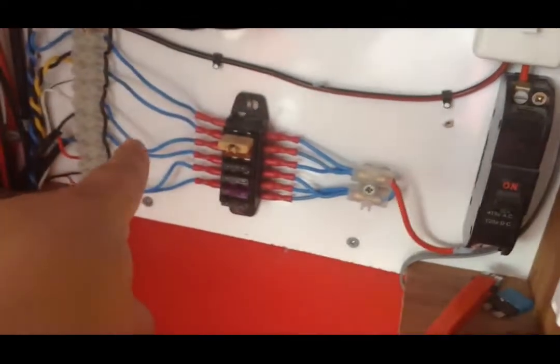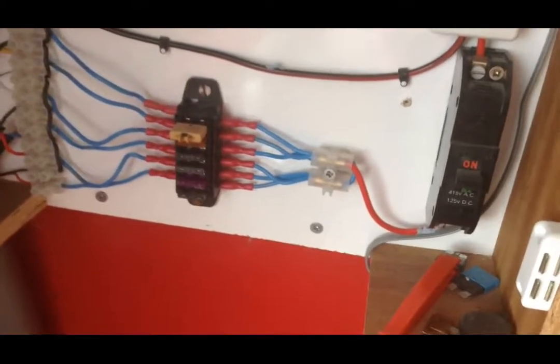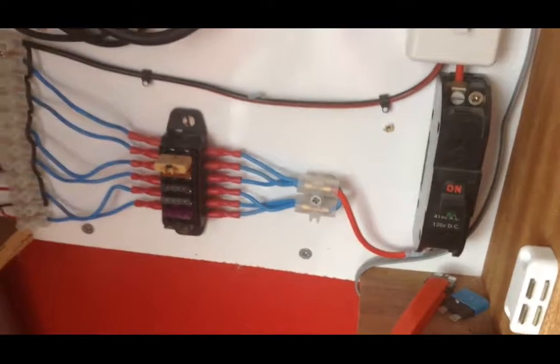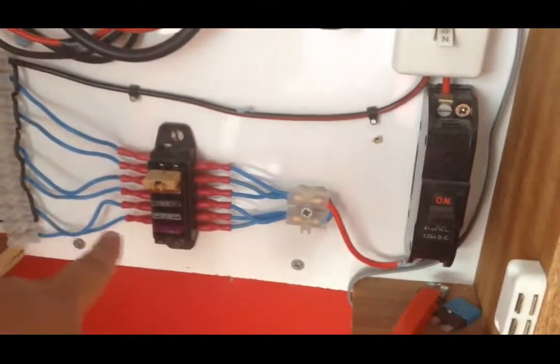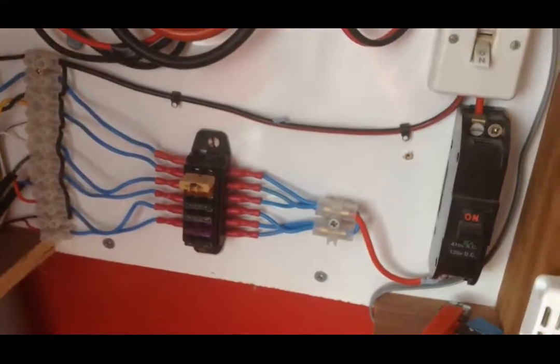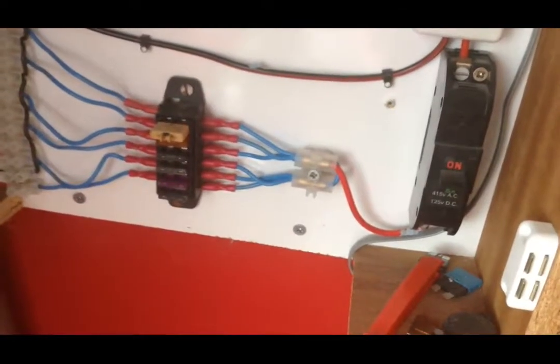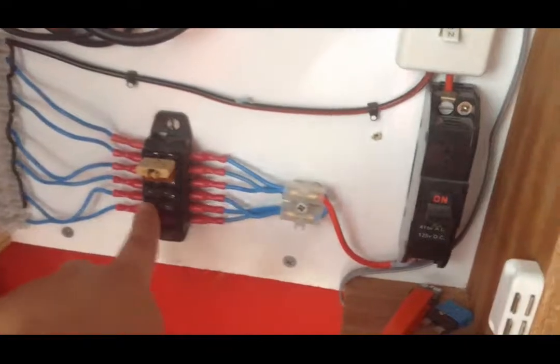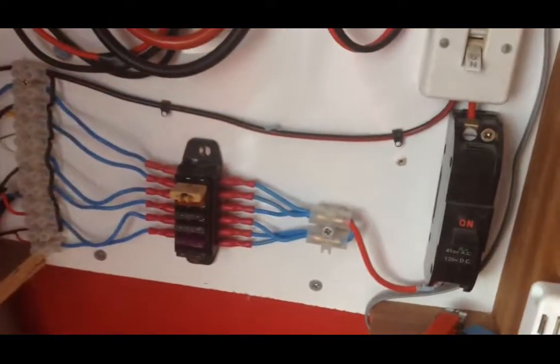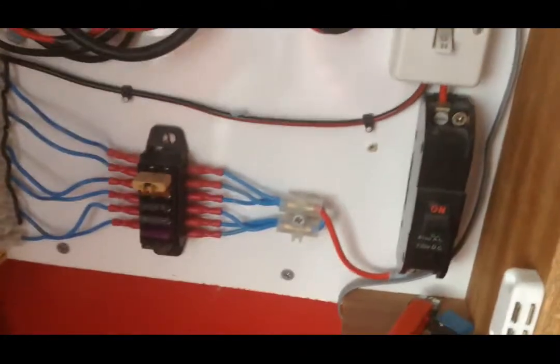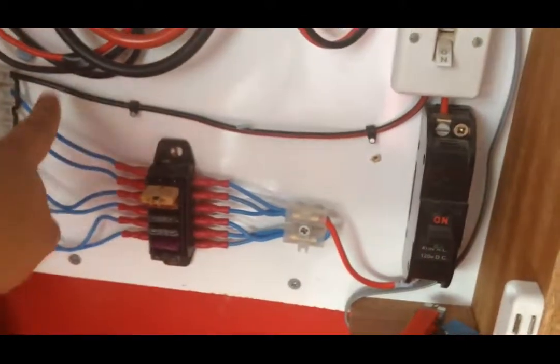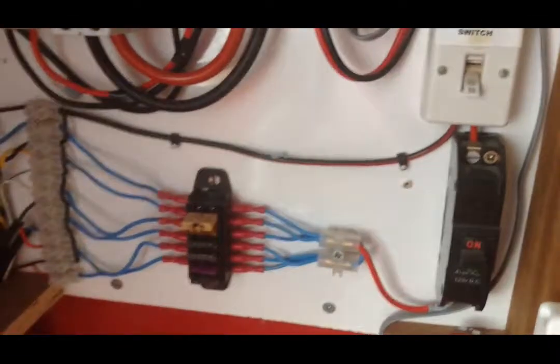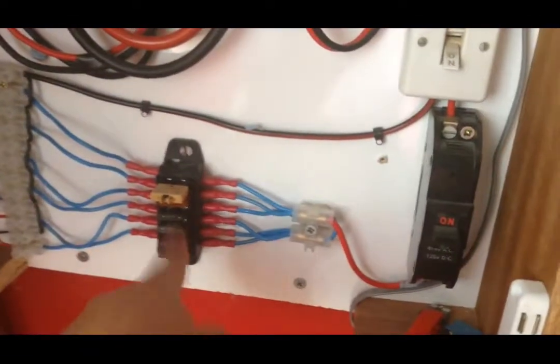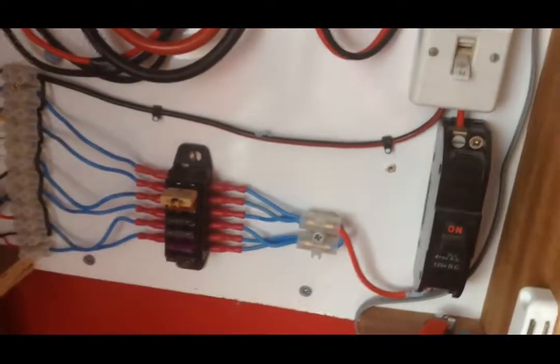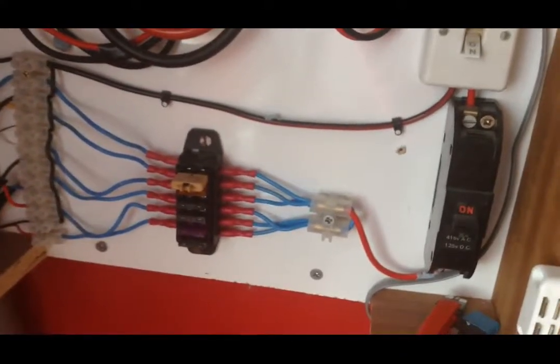It might be cheaper just to have one fuse or breaker, but if everything's wired together and one thing goes wrong, it cuts power to everything. So that might be very inconvenient. So it's better to use one fuse or breaker for each thing or each group of things that you're using. Also, if you wire things separately, you can choose the correct value fuse for each thing. So if you have a load of low power things, then you can fit a low value fuse and keep the high powered thing wired to a higher value fuse. That way, if the low power thing went wrong but didn't draw enough to trip the fuse of the high power thing, you could have issues with that. So that's why that is the way it is.